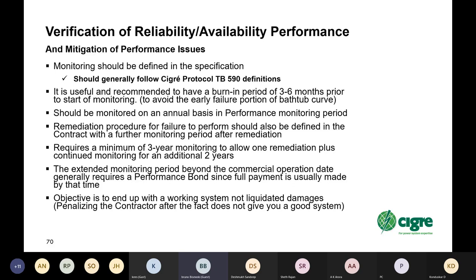Verification of reliability, availability, performance. Here again, the monitoring should be defined in the specification. Generally, the terms should follow the CIGRE protocol defined in Technical Brochure 590. It's useful to have a burn-in period of 3 to 6 months prior to the start of monitoring so that you avoid the early failure portion of the bathtub curve and really evaluate fairly the reliability of the system. It should be monitored on an annual basis in the performance monitoring period.